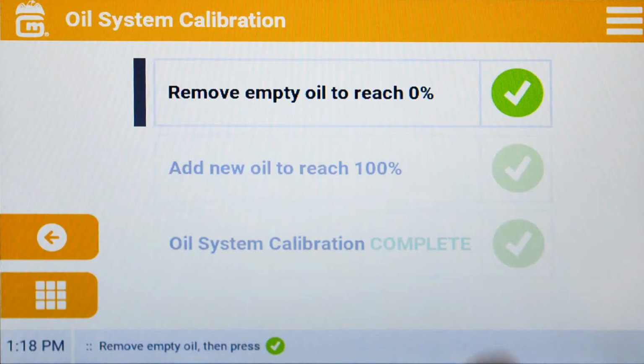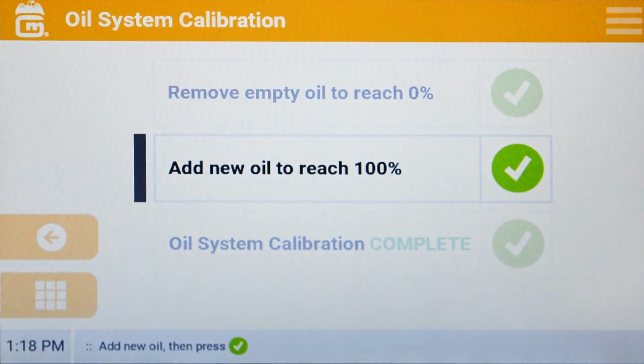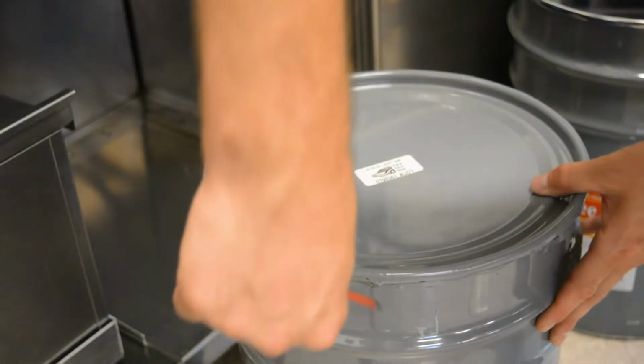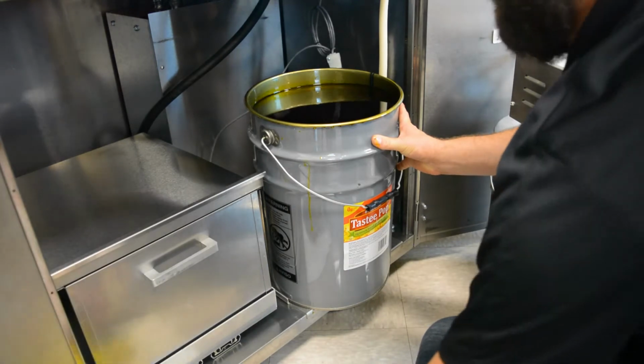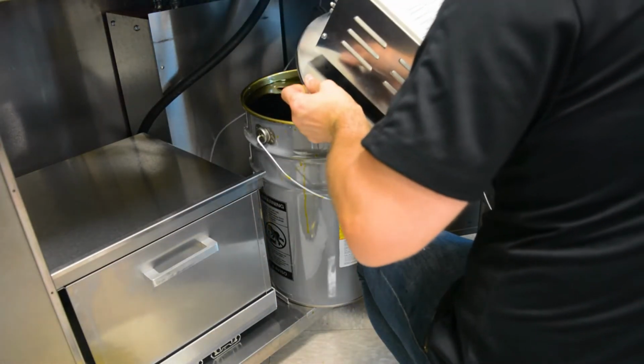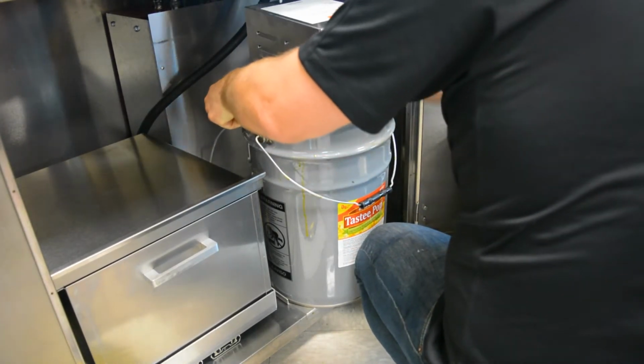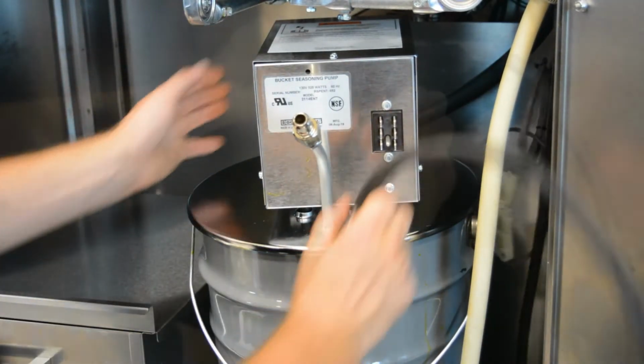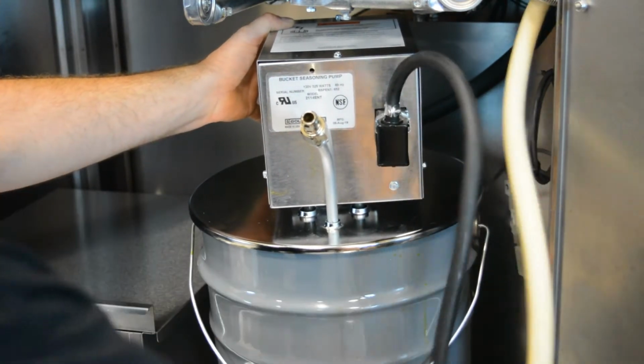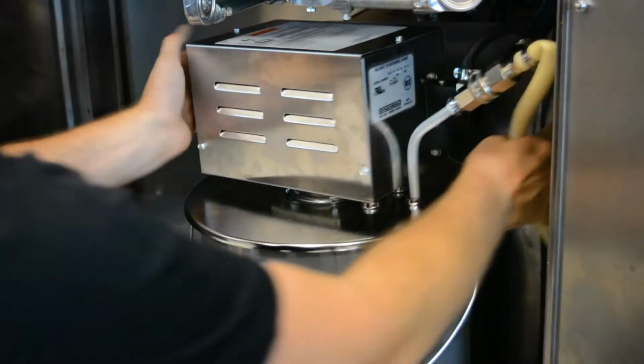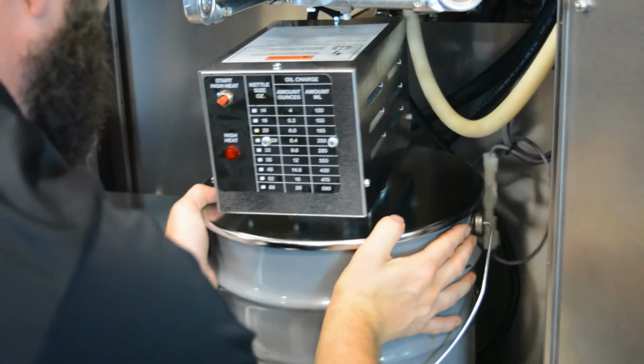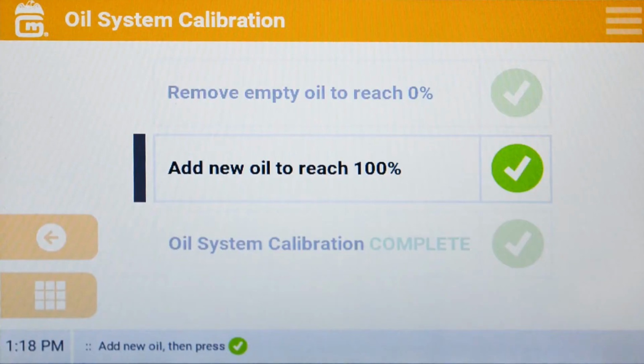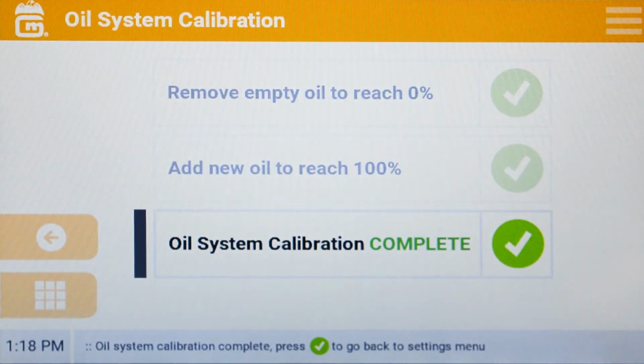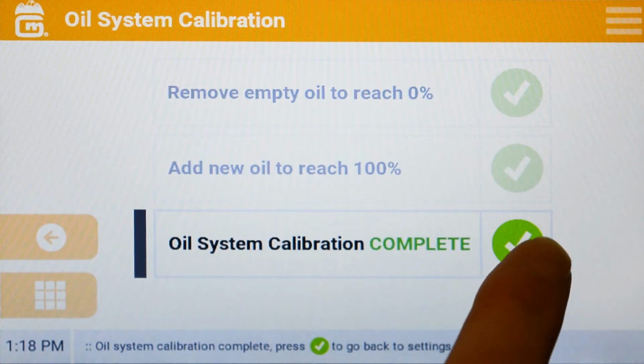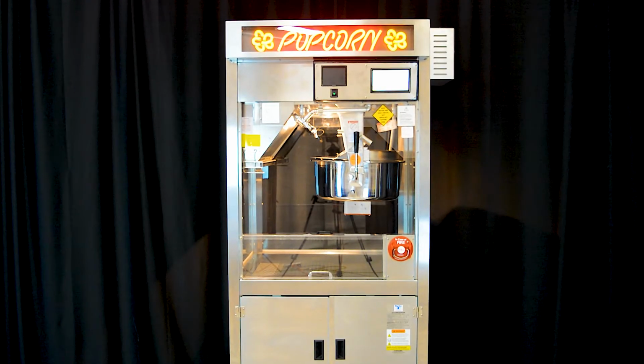With an empty bucket and motor pump on the sensor plate, press OK at the Remove Empty Oil to reach 0% prompt. Next, open a full bucket of oil and place the oil and pump assemblies onto the sensor plate. Once installed, confirm by pressing OK at the Add New Oil to reach 100% prompt. You have now calibrated the oil level. Press OK to confirm. Now that your oil level is set, you will need to calibrate the pump.